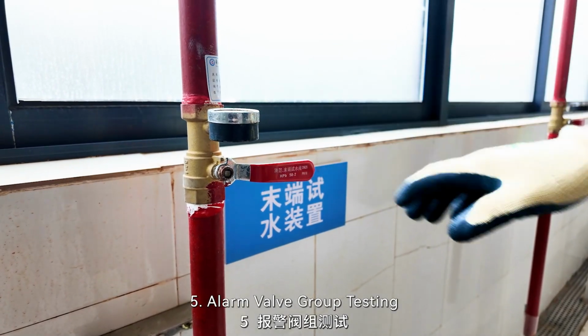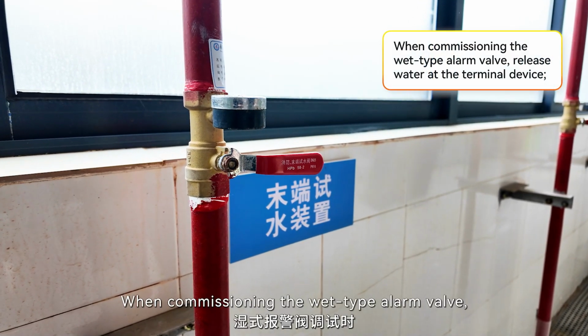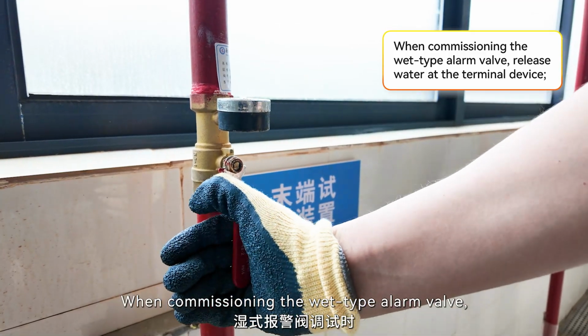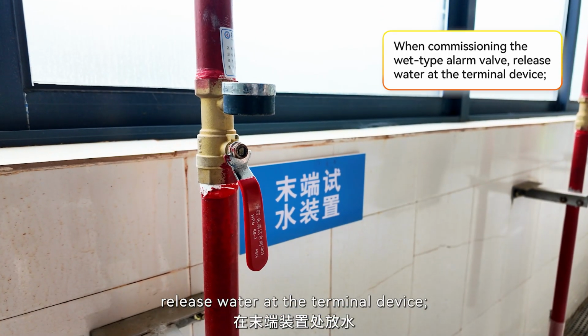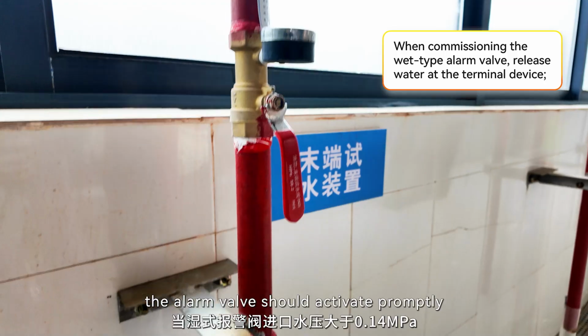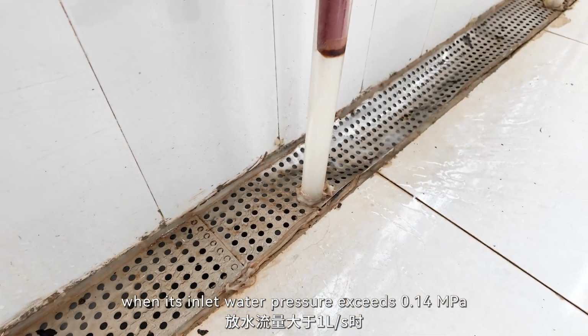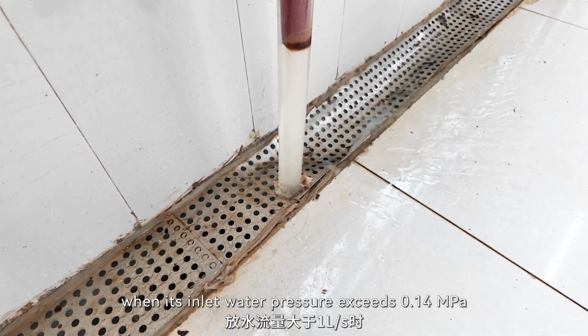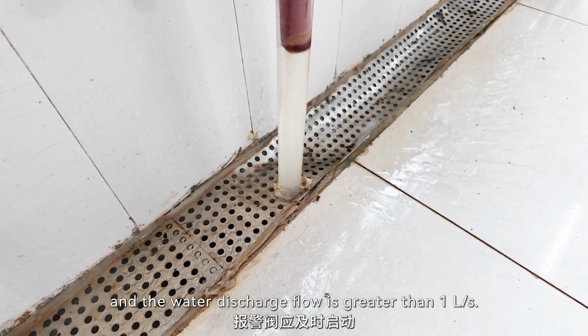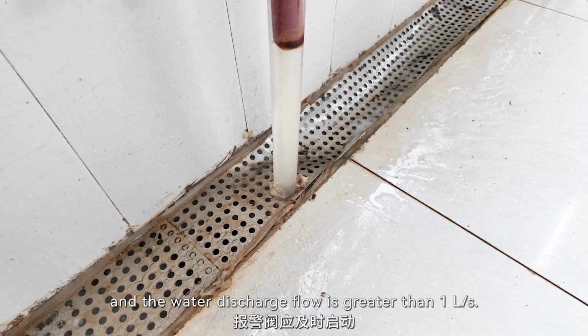5. Alarm valve group testing. When commissioning the wet-type alarm valve, release water at the terminal device. The alarm valve should activate promptly when its inlet water pressure exceeds 0.14 megapascal and the water discharge flow is greater than 1 liter per second.